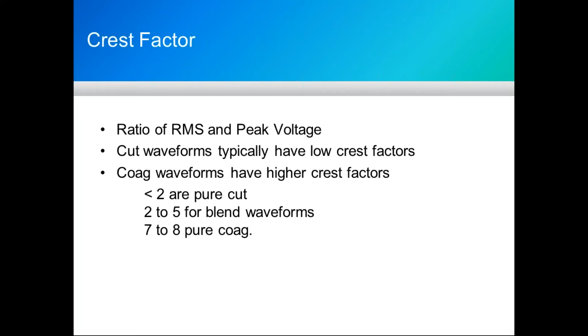The crest factor is the ratio of the peak voltage to the RMS voltage. Cut waveforms typically have low crest factors. Coag waveforms typically have high crest factors. And then here are some ranges.